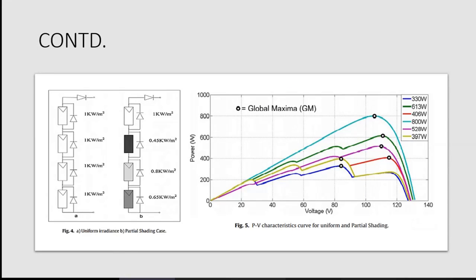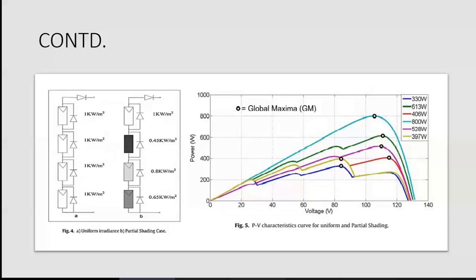There is a diagram here showing the uniform radiance and partial shading cases. As previously mentioned, we use bypass diodes for partial shading conditions so that they don't disturb the rest of the PV system. On the right side, we have the PV characteristics for uniform and partial shading. The light blue line is for uniform radiance, and the other lines show different irradiance levels under partial shading conditions.